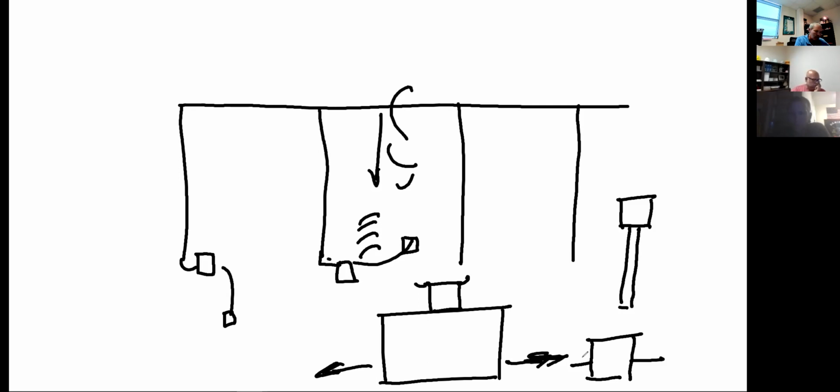Okay, what's the distance you can go on that? With high power, depending on soil conditions, I'd say maybe 200 feet. Oh, wow. Before you get to your next piece. In direct connect, you're definitely going to boost that up, 300 or 400 feet until you get loss of signal. Direct connect's going to help you out a ton there.